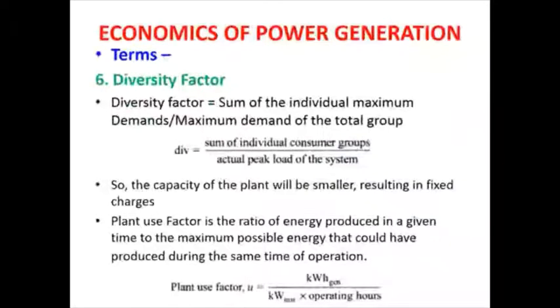Then sixth, diversity factor. It is the sum of the individual maximum demands divided by the maximum demand of the total group. Now whenever there is a diversity factor, we require one or more maximum demands. So this will be equal to the maximum connections of a particular plant, or the maximum utilization of a particular area where n number of houses are present. So it is equal to the sum of individual consumer groups divided by the actual peak load of the system. So the capacity of the plant will be smaller, resulting in lower fixed charges.